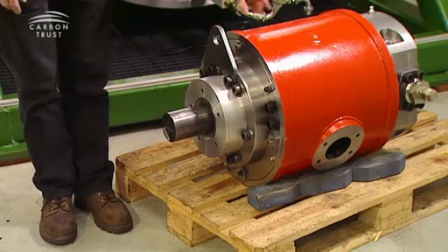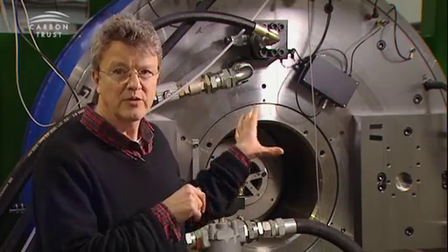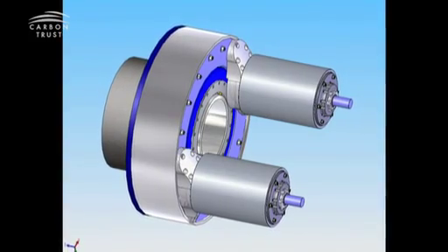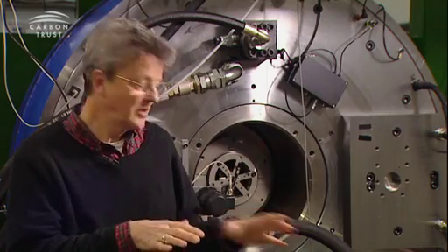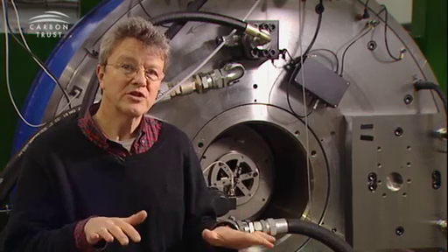This is a very large hydraulic motor — digital displacement. The idea is to have one of these pumps driven by the wind turbine rotor, driving two of these motors. Maybe the wind speed is only 6 or 7 metres per second, which is quite low for a wind turbine — we can turn one of these off so we only have one generator. That immediately reduces the losses even further. It could, in principle, be applied at any area where you want to transmit shaft power.